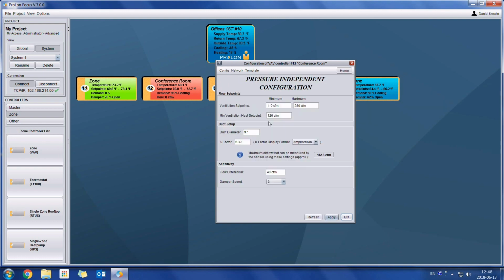If I double click on it, here we have our minimum CFMs, maximum CFMs, and the reheat CFM. So essentially when the duct heater turns on, we have a new minimum flow on the VAV controller. And here we have our duct setup, where people can put the duct diameter and the K factor for balancing purposes.